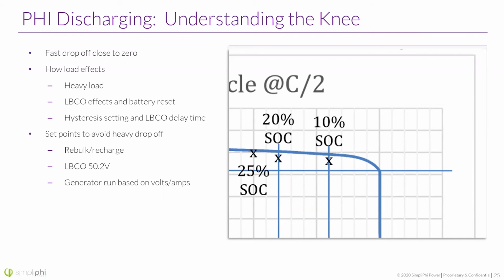What we can do to avoid that is set your rebulk or your recharge a little bit higher. Make sure you're charging if there's solar, if there's generator, if there's grid. Charge up that battery. Don't let it get to that low, that 10% state of charge, if you do have a heavy load on there. Low battery cutout, you can always set a little higher. I like my low battery cutout at 50.2. This is 80% depth of discharge or 20% state of charge. This is a great voltage to use. Again, if you're using 24 volt or 12 volt, just divide that number.